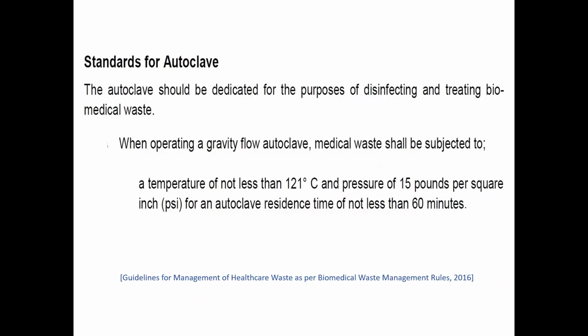And when operating this, remember some parameters. The temperature should not be less than 121 degrees Celsius and a pressure of 15 pounds per square inch. Also, a residence time of not less than 1 hour. If you remember, for disinfection of reusable items, it's around 30 minutes, but for disinfection of BMW, it should be a minimum of 1 hour. This is because BMW, as I said in the beginning, is considered infectious waste.